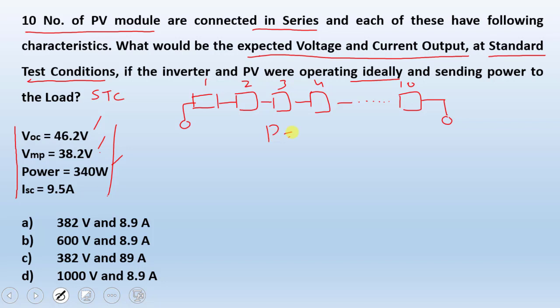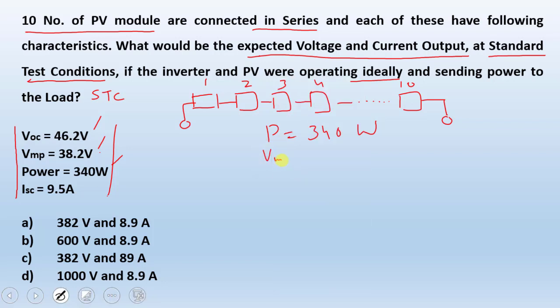What does this mean is that if the power is 340 watts, then the voltage shall be 38.2 volts. So we have power here 340 watts and we have maximum voltage 38.2. So under Standard Test Conditions, the module is operating at or delivering 340 watts and it shall be at the voltage 38.2 volts.